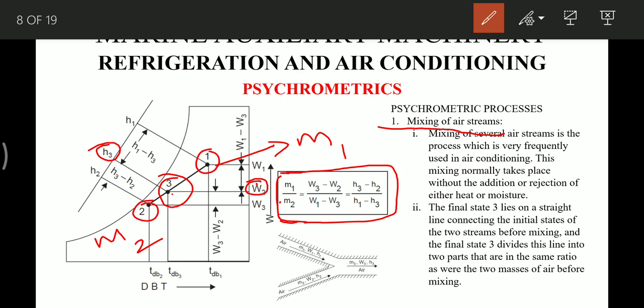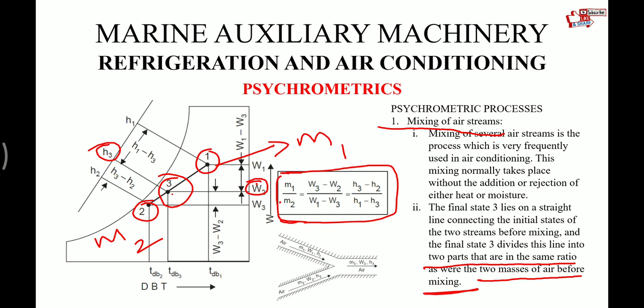Mixing of several air streams is a process very frequently used in air conditioning. This mixing normally takes place without the addition or rejection of either heat or moisture. The final state 3 lies on a straight line connecting the initial states of the two streams before mixing. The final state 3 divides this line into two parts which are in the same ratio as the two masses of air being mixed. So point 3 divides the line in the ratio of the masses in which the air is mixed.